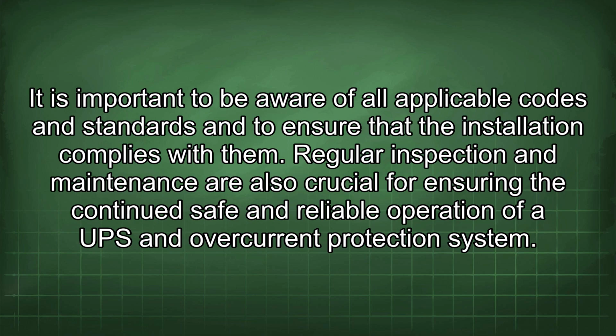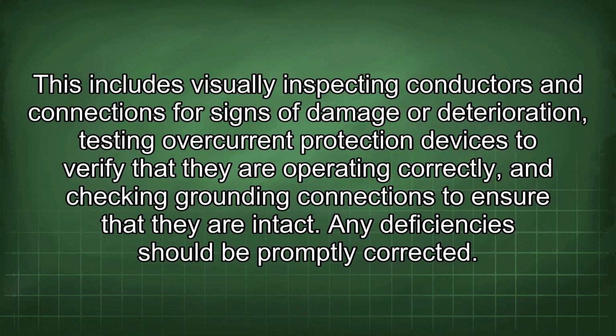Regular inspection and maintenance are also crucial for ensuring the continued safe and reliable operation of a UPS and overcurrent protection system. This includes visually inspecting conductors and connections for signs of damage or deterioration, testing overcurrent protection devices to verify that they are operating correctly, and checking grounding connections to ensure that they are intact. Any deficiencies should be promptly corrected.